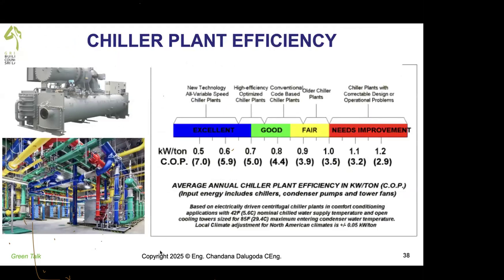Now, chiller plant efficiency. This is how chiller plant efficiency has improved. In the early days, in the 1990s, 1995, 1994, 0.8 was the limit. Now it is 0.5, 0.6. All this is full load kilowatt per ton.